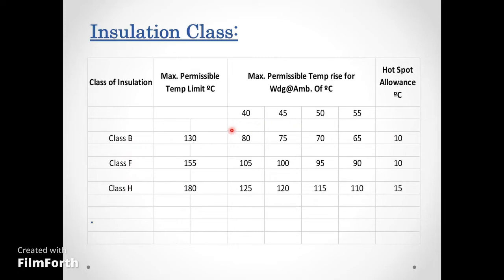For example, at 40°C ambient with an 80°C rise, the total is 120°C. From 120°C to 130°C, the 10°C margin is the hot spot allowance, accommodating localized peak temperatures inside the winding.